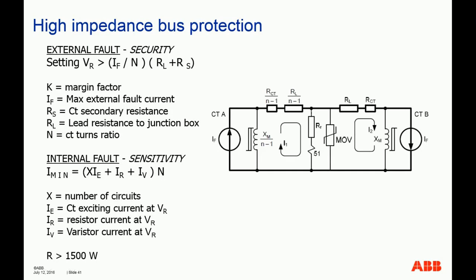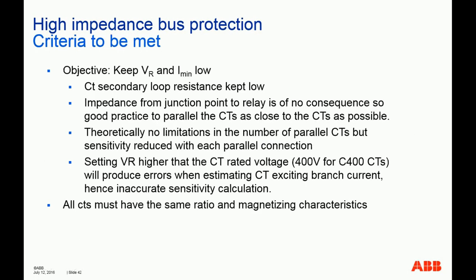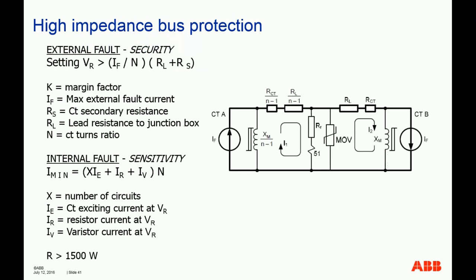So if you can try to parallel your CTs outside the yard, near the physical CT junction box, for example, then you can reduce the RL, because the resistance between the junction point to the relay terminal is negligible because of this huge 1500 ohm resistance here. Okay. And theoretically, there's no limitation in the number of parallel CTs, but remember, we need to calculate the sensitivity of this scheme. The fault current needs to be higher than the minimum current sensitivity of this scheme in order for the relay to operate.